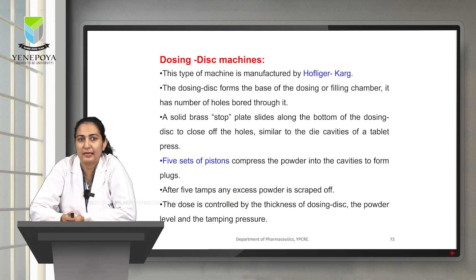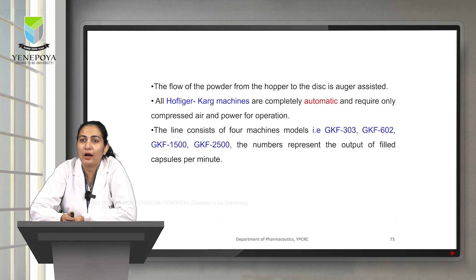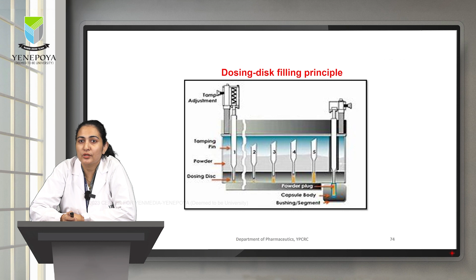The flow of powder from the hopper to the disc is auger assisted. All Hofliger Karg machines are completely automatic, and require only compressed air and power for operation. The line consists of 4 machine models, GKF 303, 602, 1500 and 2500, where the numbers represent the output of filled capsules per minute. As you can see here, this is the dosing disc filling principle. The tamps are adjusted, those are nothing but the tamping pins. The powder is placed, then the dosing disc compresses the powder, and finally the powder is ejected as a powder plug. The same powder plug can then be introduced into the capsule bodies.